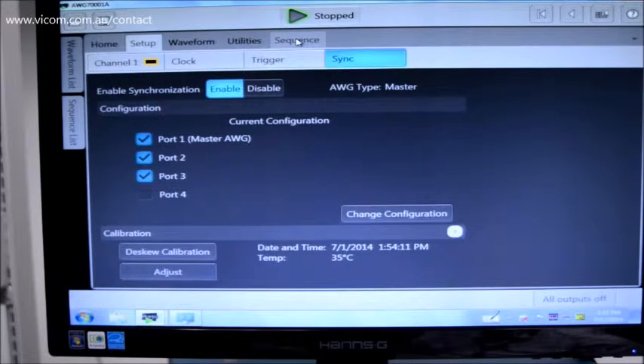So if you're using the sequencer and you want to make sure that all of the sequences from the individual AWGs are triggered at the same time, the trigger would go into the sync hub, but the master controls all of the settings required for the sample rate, basically everything except for loading the waveforms. You can load individual waveforms per AWG, but as far as running the actual outputs go, this would be run from the master. So once you've started the output, it will synchronize the rest of the AWGs.